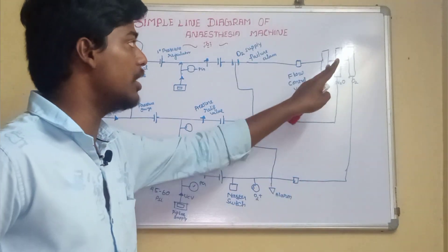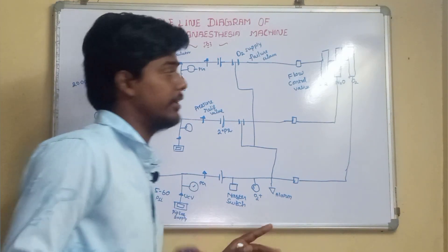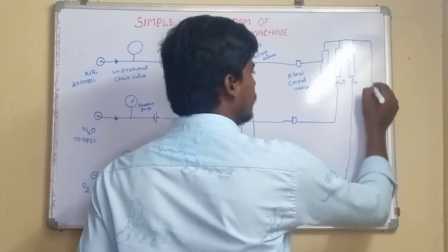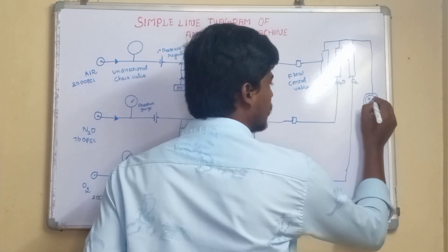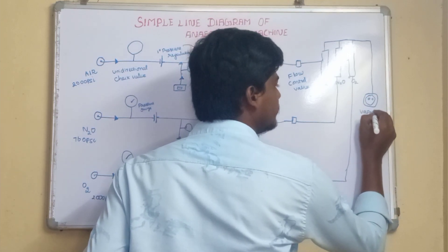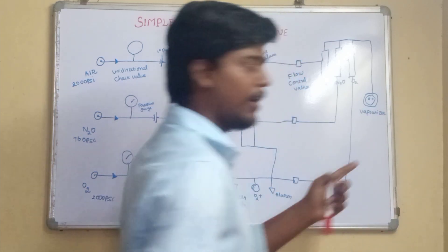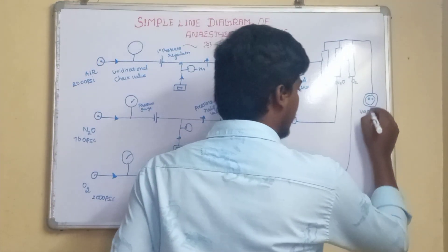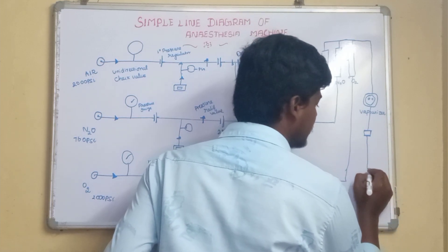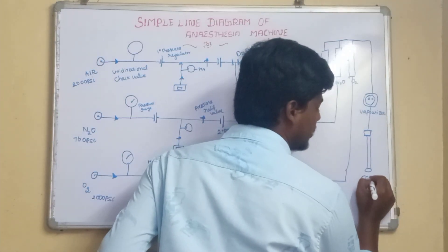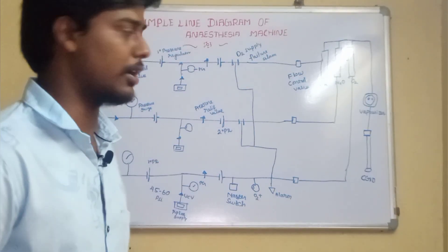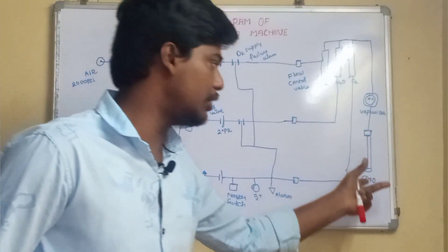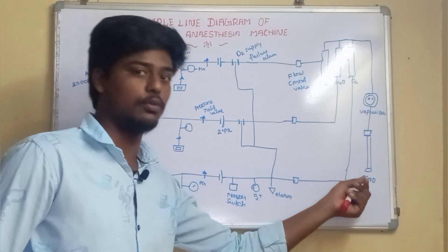The oxygen flow meter should be downstream in nature to prevent hypoxic mixture delivery. All flow meters together are connected to one important component called the vaporizer. The vaporizer vaporizes inhalation anesthetic agents. After the vaporizer, there is a pop-off valve, and then the last part is the common gas outlet, through which oxygen and all other medical gases travel.